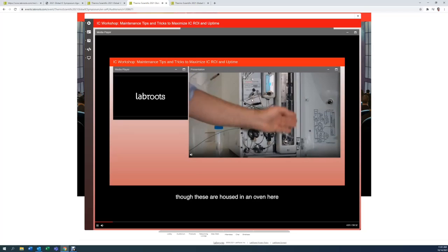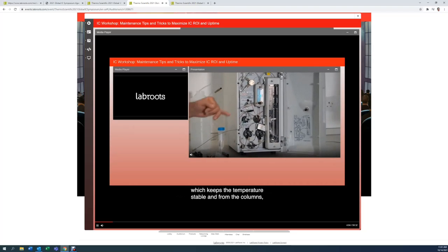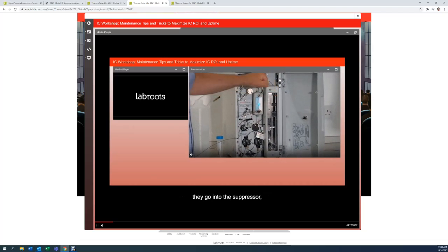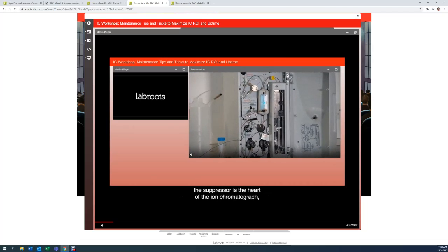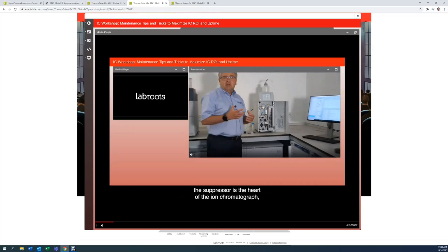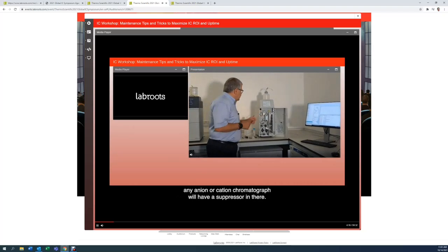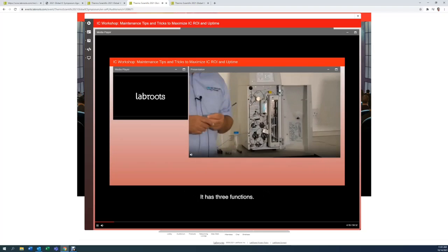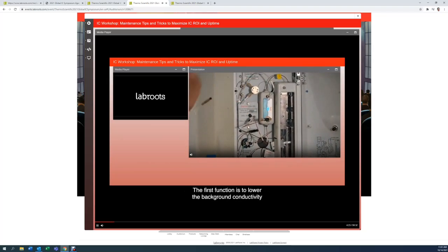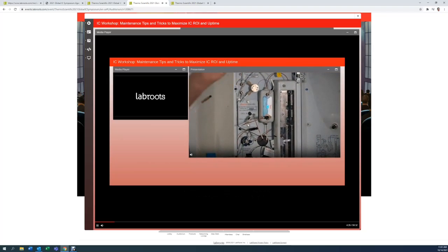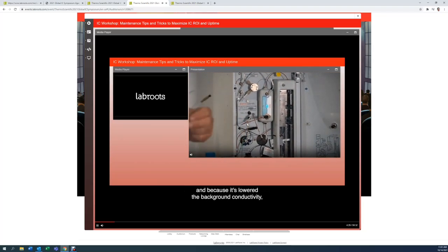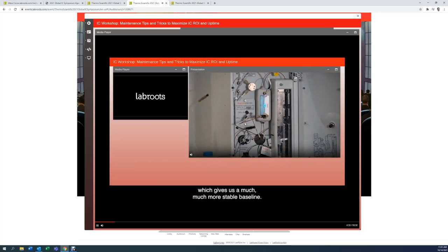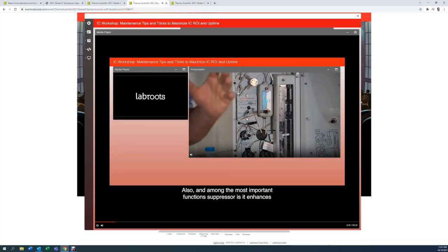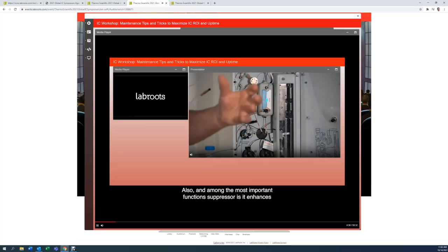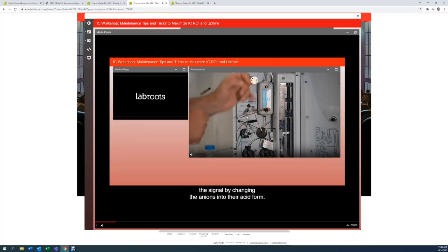These are housed in an oven here, which keeps the temperature stable. And from the columns, they go into the suppressor. The suppressor is the heart of the ion chromatograph. Any anion or cation ion chromatograph would have a suppressor in there. It has three functions. The first function is to lower the background conductivity. And because it's lowered the background conductivity, we're also lowering the background noise, which gives us a much more stable baseline. Also, and one of the most important features of the suppressor, it enhances the signal. By changing the anions into their acid form, we get a significant increase in the response.